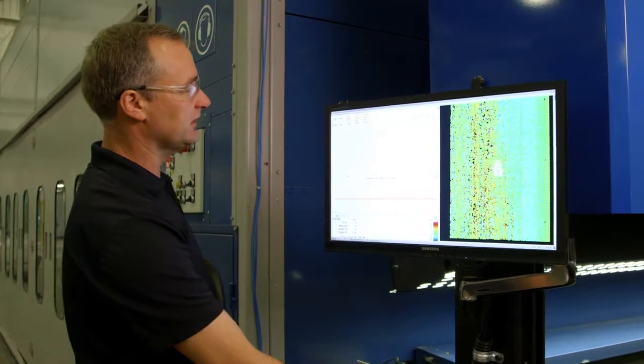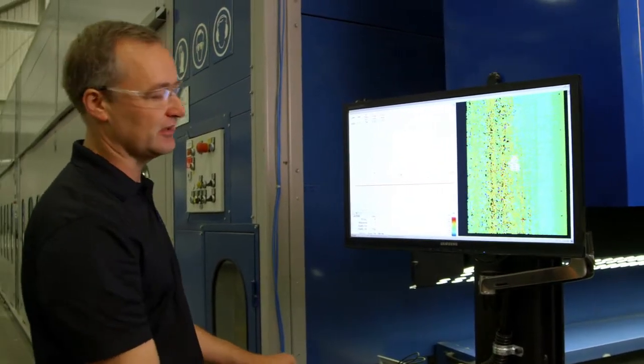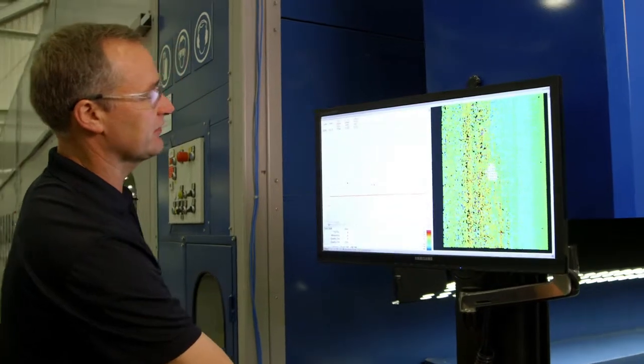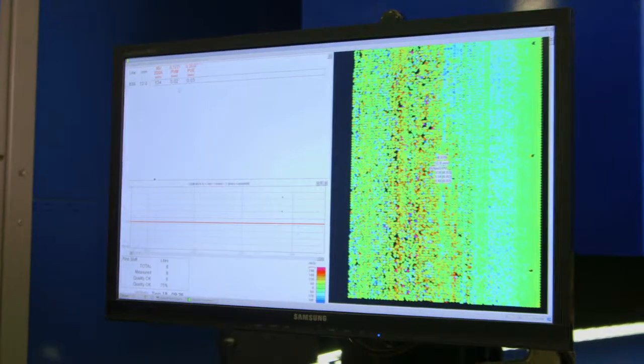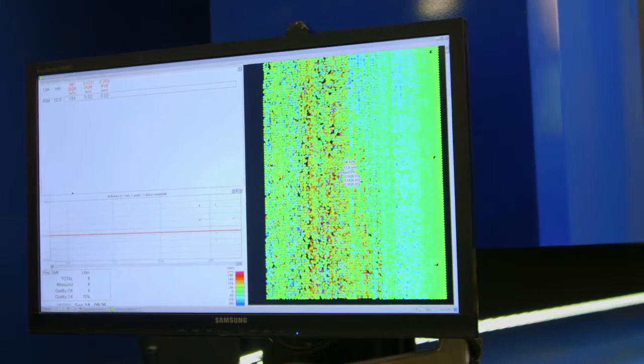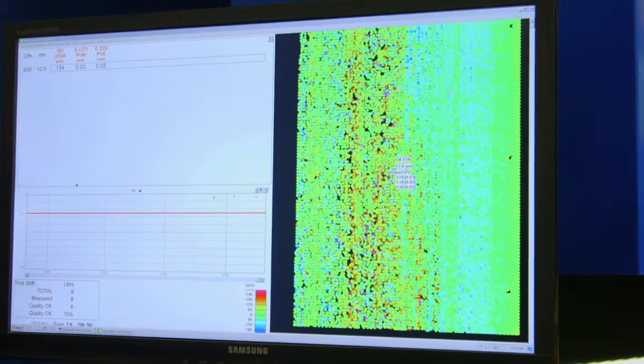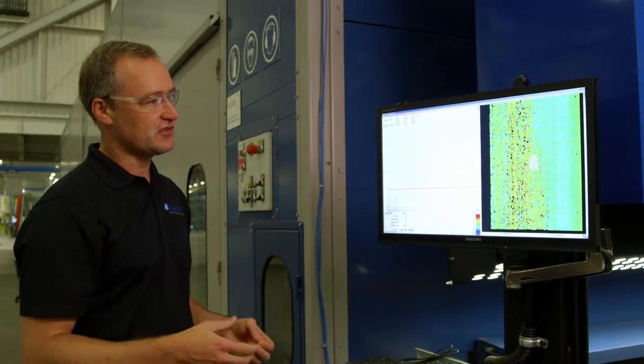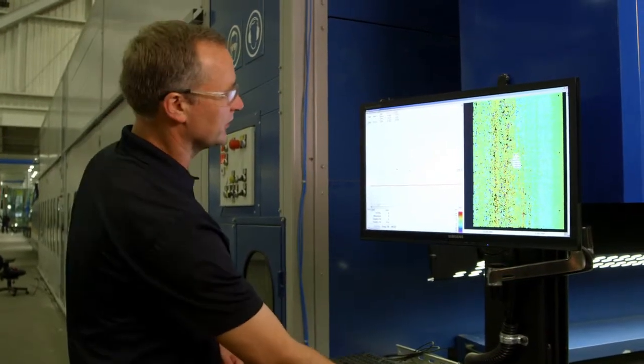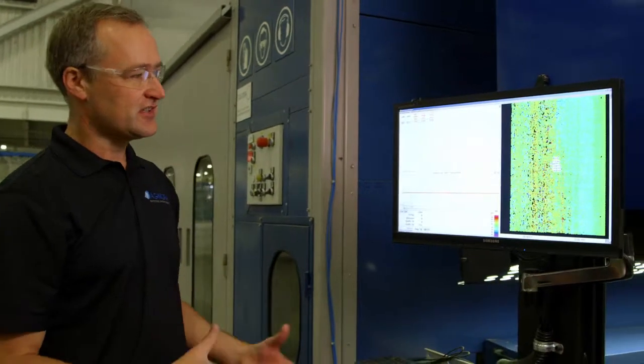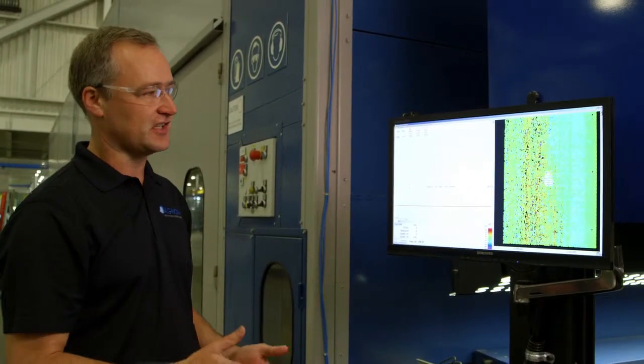The data is displayed to the operator as peak to valley measurements and as a millidiopter measurement. The peak to valley measurements, ones here, are the ones that reflect roller waves, so the amount of variation that goes up and down within the glass. The glass is also physically displayed and reflected as a number in terms of millidiopters. This number is associated with the curvature of the glass at any given point. So the coloration on this side shows the variation from the norm at any small piece within the glass. It's approximately done on a 1-inch glass basis.